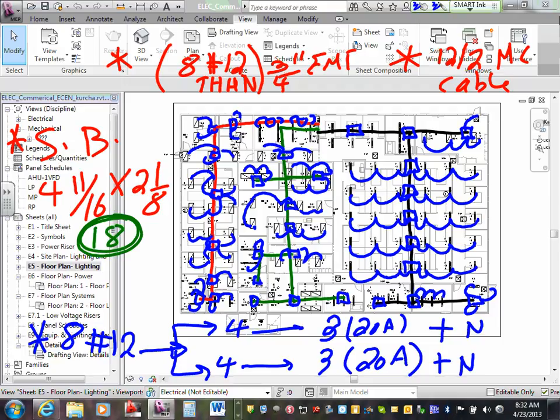I took your project, by the way. I took Jeff's project. Jeff has 24 lighting circuits. So 24 lighting circuits, guys, can get me a 3 to 4 conduit system. I can fill all the conductors going back all the way to the panel. So what I did, I decided to use 3 conduits. I could have used 4. If you circuit it right, all the circuits should be in one area. You can't bring a circuit from here all the way to the other side, with a lighting fixture here and a lighting fixture there, and put them in the same circuit. You can, I guess, but then you have to move them through the conduit system.